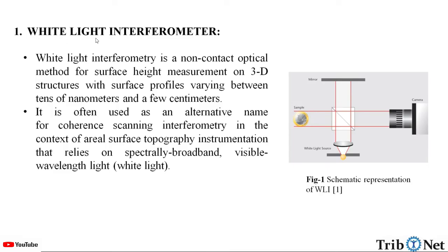White Light Interferometry is a non-contact optical method for surface height measurement on 3D structures with surface profiles varying between tens of nanometers and a few centimeters. It is often used as an alternative name for coherence scanning interferometry in the context of areal surface topography instrumentation that relies on spectrally broadband visible wavelength light — that is, the white light.